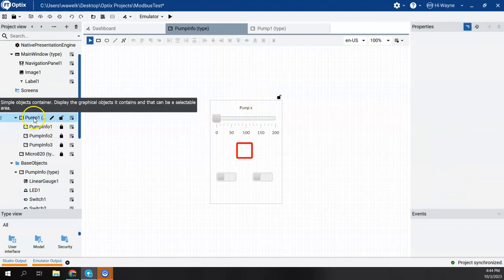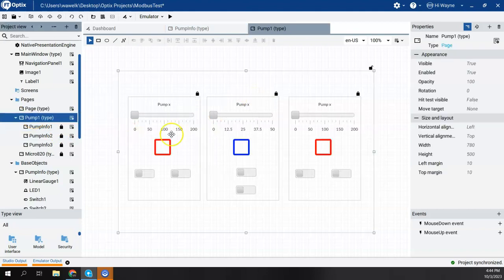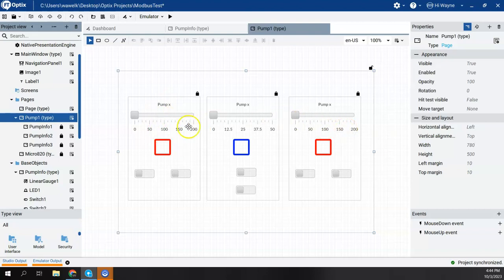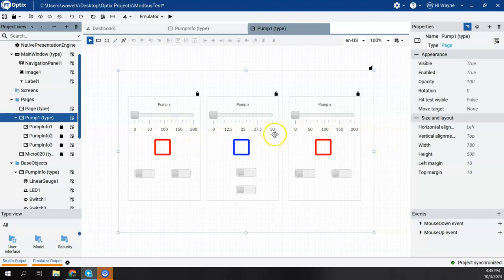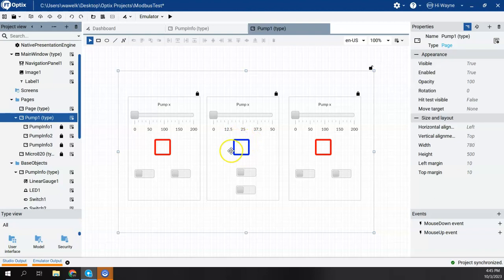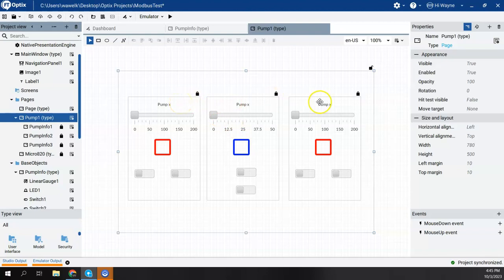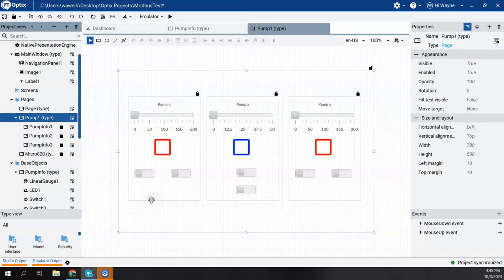Well, if I come back to my Pump1 screen, we can see that in the cases of the left and right most widgets, it changed it to 200 and it changed it to a rectangle. It did not change the scale on the one in the middle because I already customized it. It also did change the LED to a square, so it did update that property, but it kept it blue because I had already told it to be a blue LED. So this is pretty nice and interesting. We can create one object and then deploy it throughout and then customize it individually. But then certain properties from the parent will get permeated throughout all the instances that have been used throughout the Optix project.